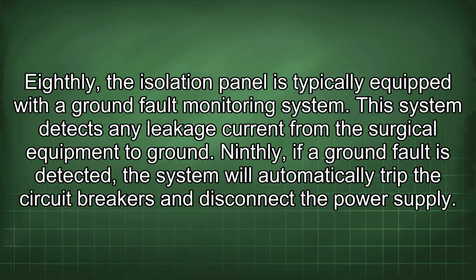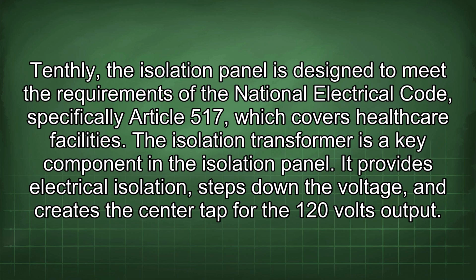Eighthly, the isolation panel is typically equipped with a ground fault monitoring system. This system detects any leakage current from the surgical equipment to ground. Ninthly, if a ground fault is detected, the system will automatically trip the circuit breakers and disconnect the power supply. Tenthly, the isolation panel is designed to meet the requirements of the National Electrical Code, specifically Article 517, which covers healthcare facilities.